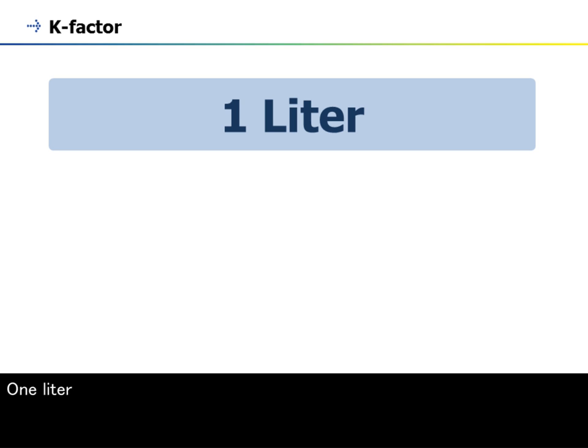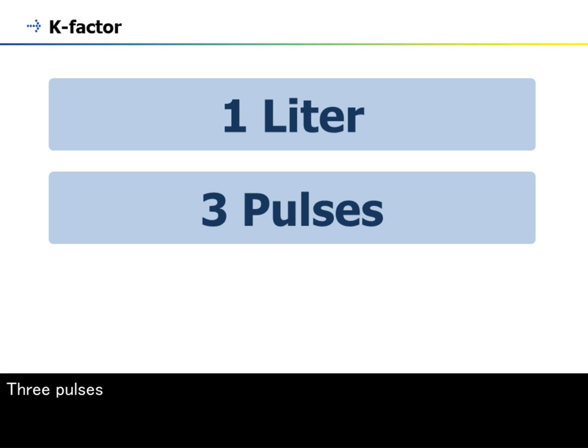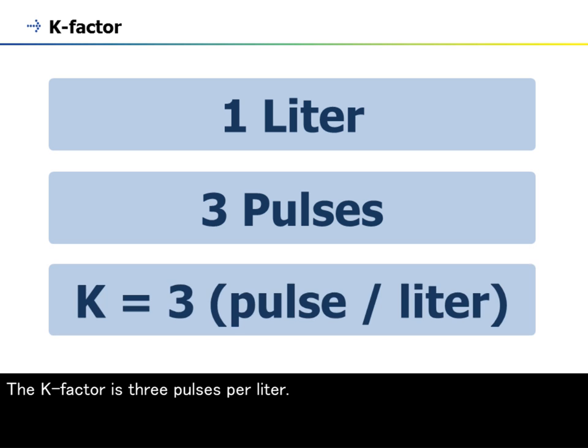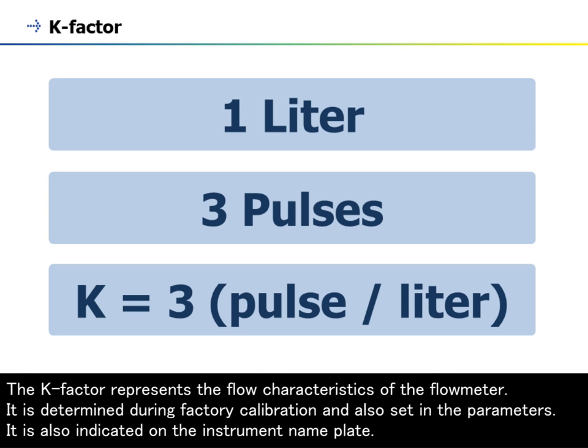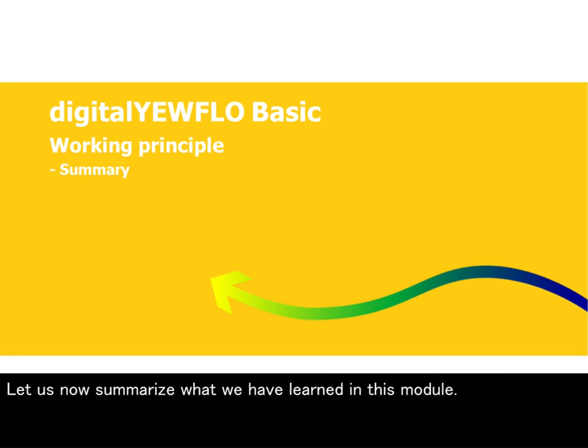The K-factor is calculated as shown. One liter, three pulses. The K-factor is three pulses per liter. The K-factor represents the flow characteristics of the flow meter. It is determined during factory calibration and also set in the parameters. It is also indicated on the instrument nameplate.